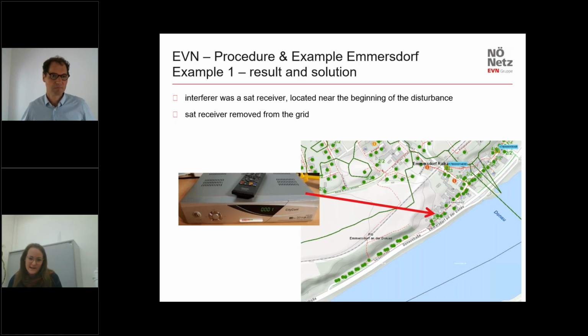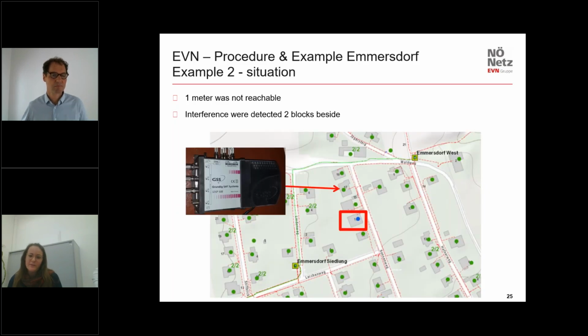Next, we have another example, also in the same area but on another substation. There we only failed to reach 1 meter, and the procedure was nearly the same. The technician also measured with the PLT device in the grid and found noise 2 blocks beside this meter. Here you can see a picture of the noise source.